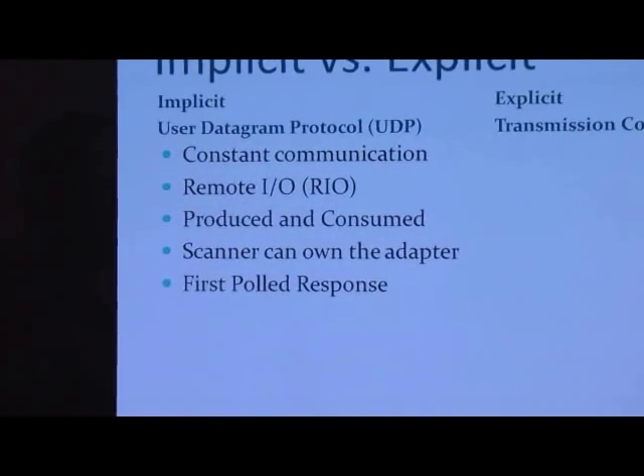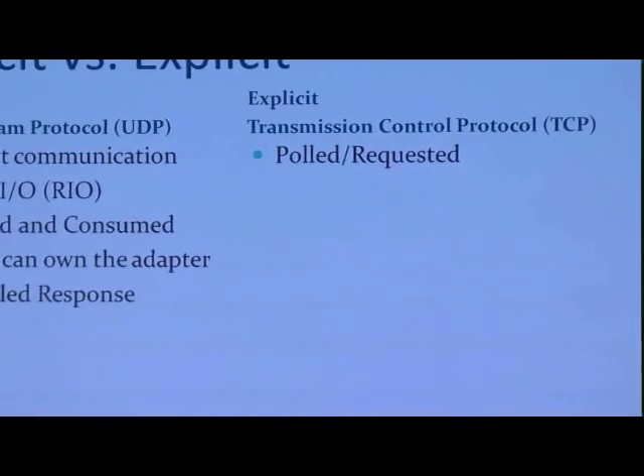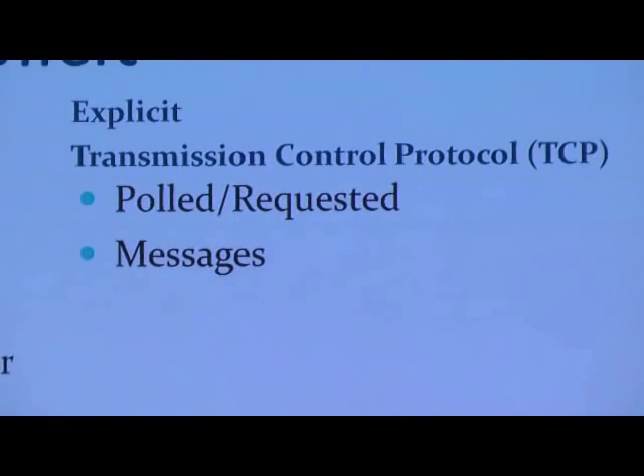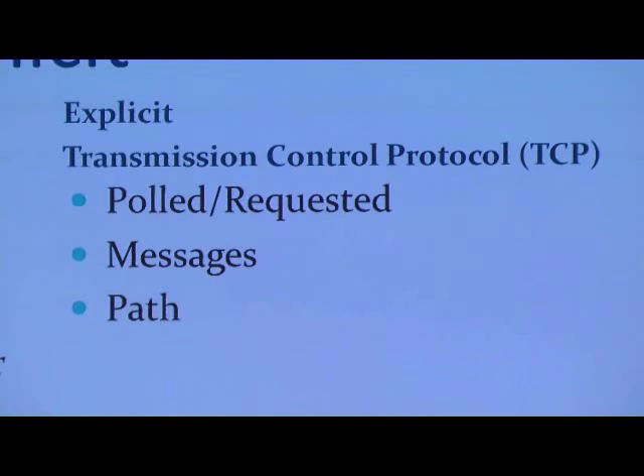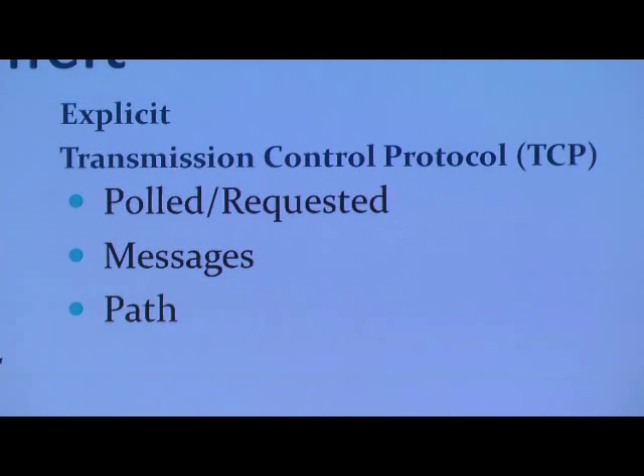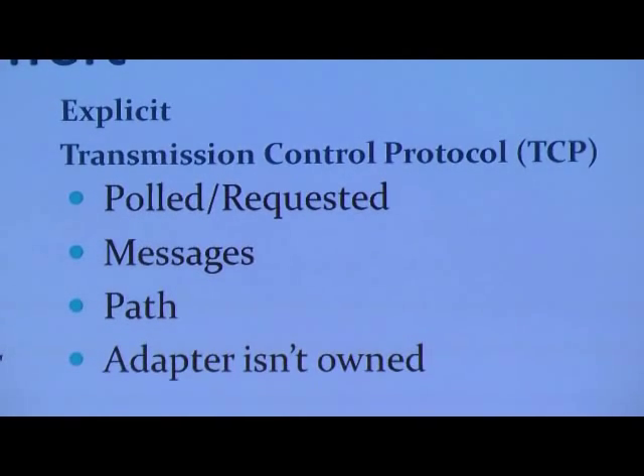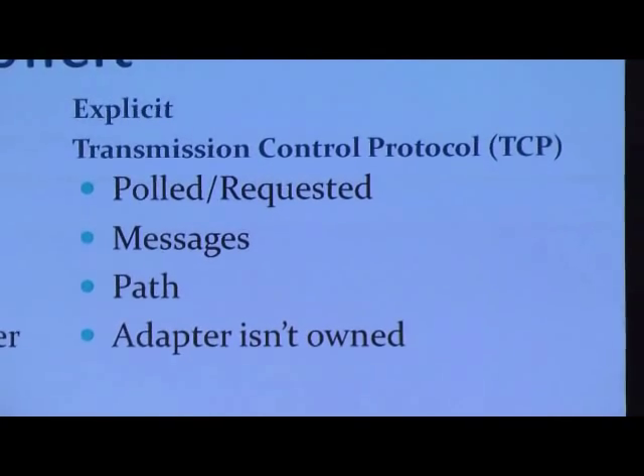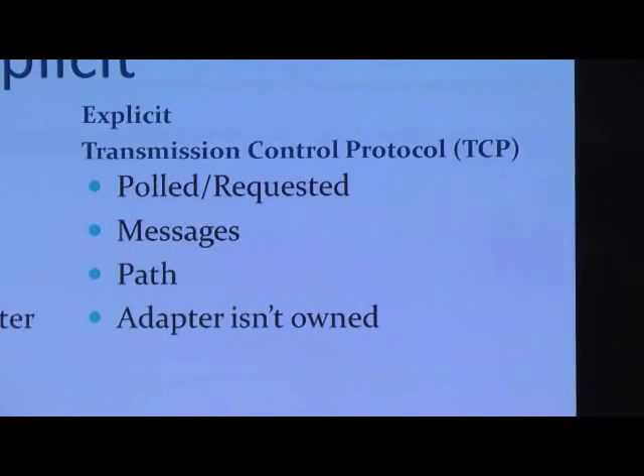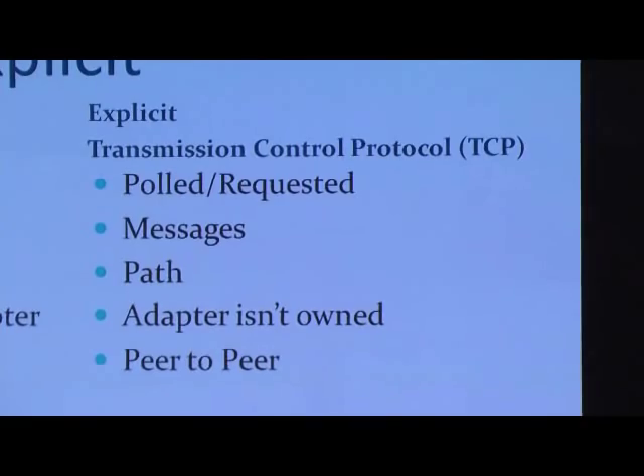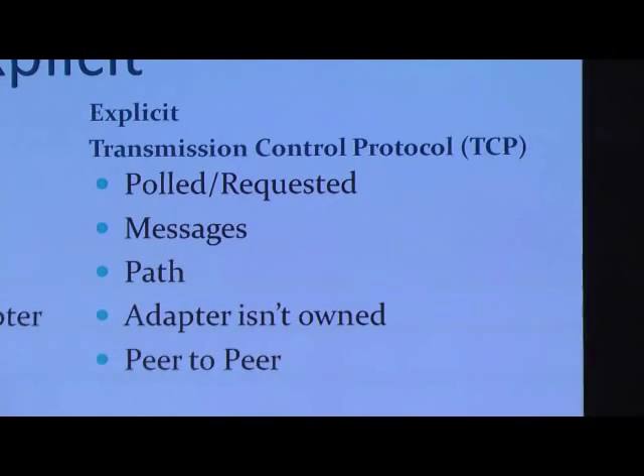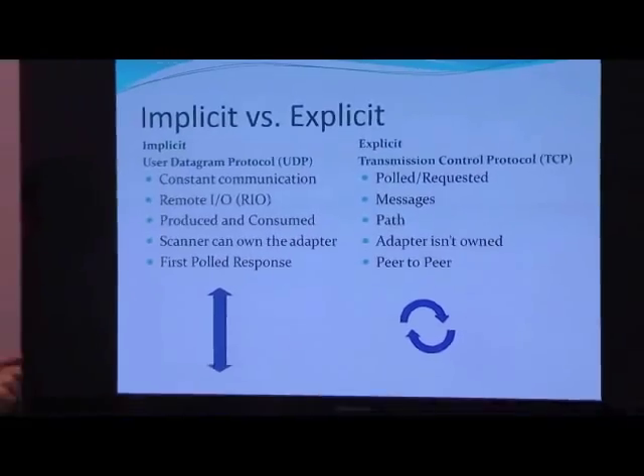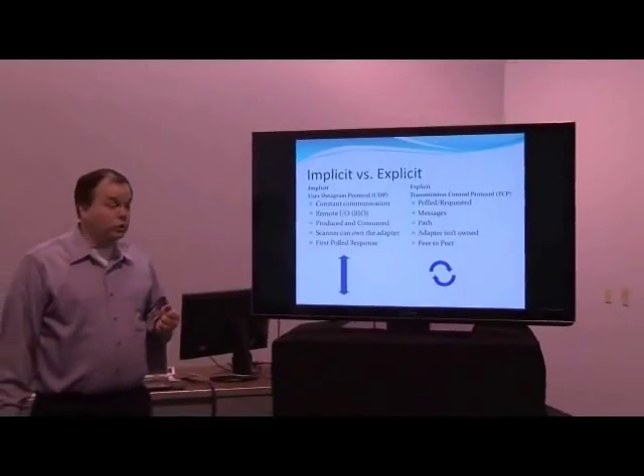With explicit communication, it is a polled or requested communication — the most familiar form being just a read or write message in PLCs. It requires a path and a definition of the object structure, the instances, and the attributes of the object. In this case, the scanner opens a connection, takes the message it needs, and then closes the connection. It is based more on a peer-to-peer methodology. Think of implicit as a pipe permanently connected between two devices, and an explicit message as a softball thrown between the two devices with information.